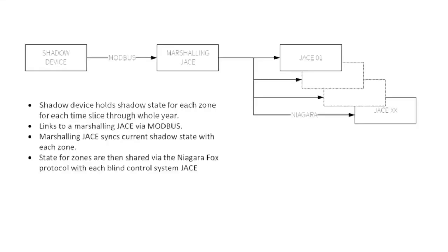We use a product called a JACE for this. A JACE is a device manufactured by a company called Tridium, and it's used in all sorts of scenarios. If you come across Trend or Honeywell as a BMS, the controllers now are basically Tridium JACEs with a Honeywell or Trend badge on the front. They're used in BMS situations, and we use them as really intelligent logic control devices.